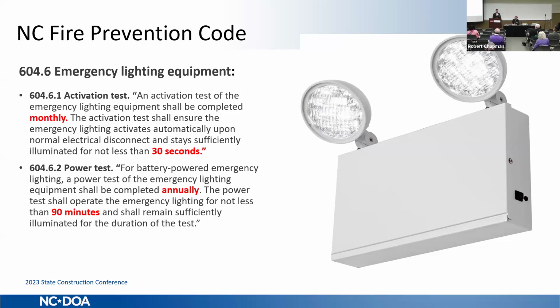And sometimes they use night lights for a facility. That's great for a 24-hour facility like a hospital or something like that. But there are buildings out there that are quite large where you don't need to leave the lights burning all the time. If you use a UL 924 listed little module, you can turn those on and off with the normal lights, and it will still give you the testing requirements that this code is requiring. And then there is another thing too. We think about all the maintenance that has to be done, and they have busy schedules. They have to understand all these references to the code. So there's quite a lot of things that our maintenance folks have to take care of. One thing that manufacturers typically offer with emergency battery units is the self-test feature, a very small upgrade. But what it does is it complies with what this code is requiring.